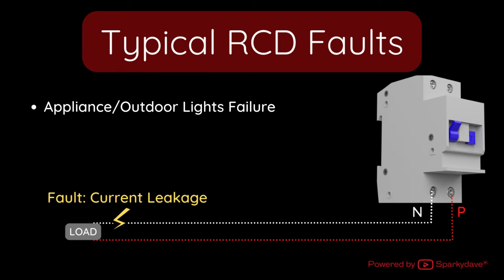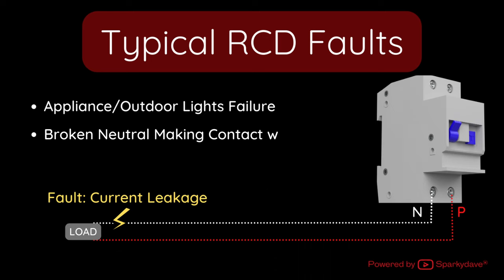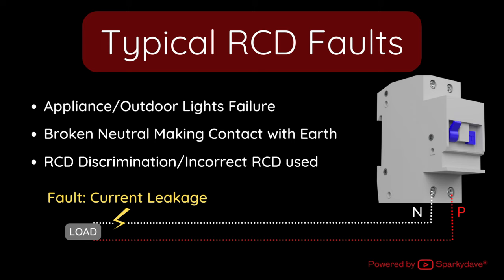Most of the time an appliance will have become faulty. Less commonly, a neutral cable may have broken and would be making contact with earth somewhere behind a fitting. Even less common could be a discrimination issue with downstream or upstream RCDs, or unsuitably rated RCDs — I will explain these in a separate video soon.